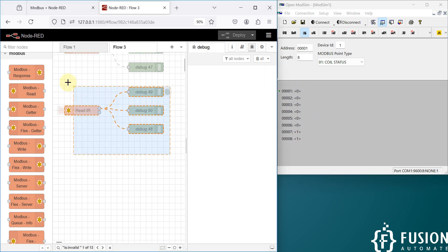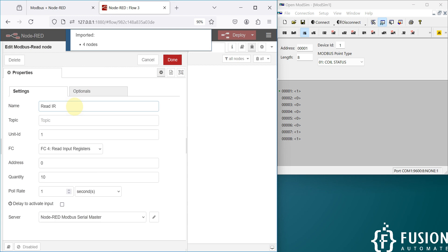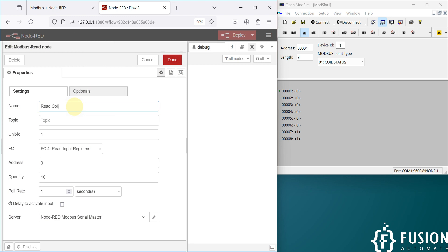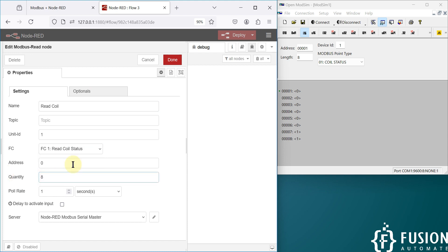I'm going to copy this node and paste it here. We are going to read the coil — so 'read coil'. In the function code we have to select function code one to read the coil status. The quantity we want to read is eight, the starting address is zero, and the poll rate is one second.